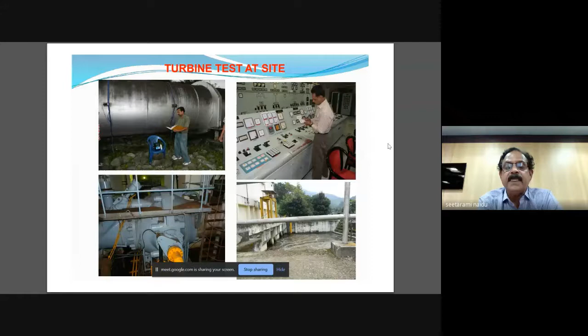This investigation was done in 1998. I'm lucky that I was also part of this investigation. Their problem was that they had 3 units rated at 35 megawatt, 105 megawatt total, commissioned in 1977, inaugurated by Srimati Indira Gandhi, then Prime Minister of India, but they never reached 105 megawatt when using 3 units; maximum 95 or 96 megawatt they could get. The reason for the loss of power and higher discharge was that the surge tank was exposed, and we could see the fully exposed surge tank and air pockets, a mixture of air and water entering through the surge tank. When we asked for more and more power generation, it was in fact reducing the efficiency. So this was a problem.